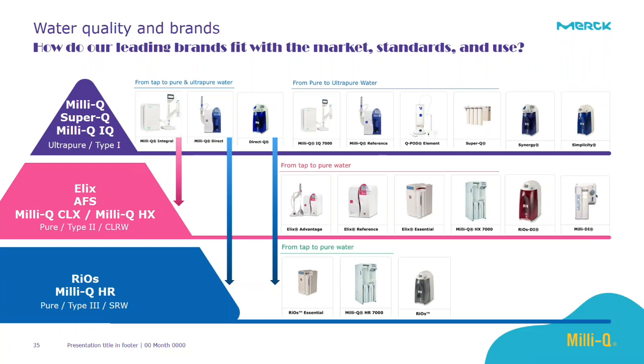Finally, we have the systems which produce type 1 ultra pure water, and it depends on the feed water type. If you are feeding the system with tap water, we have the MilliQ Integral, the MilliQ Direct, and the Direct Q system. But if you have a source of purified water, we have another group of instruments which produce type 1 water from purified water, like the recently launched MilliQ IQ7000, MilliQ Reference, QPod Element, Super Q, which can produce up to 12 liters per minute of ultra pure water, and the Synergy and Simplicity systems.